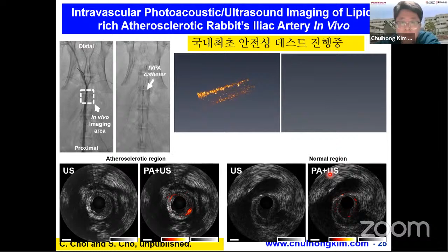So all these problems actually come from when we combine optical excitation tools and acoustic detectors. So all this headache comes from there. But if we develop an optically transparent ultrasound transducer, all light can penetrate through. Then in that case, we can seamlessly combine many optical and acoustic imaging tools. As you can see in this slide, we developed an ultrasound transducer which is optically transparent. It's about 70% transparency in near infrared or visible ranges.